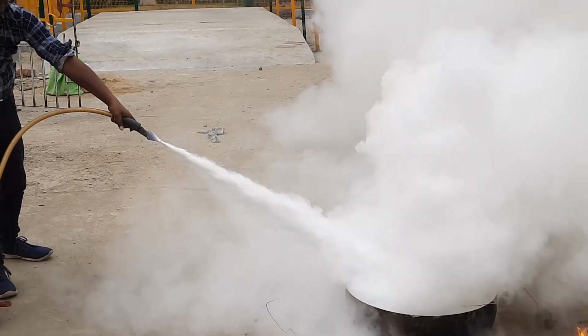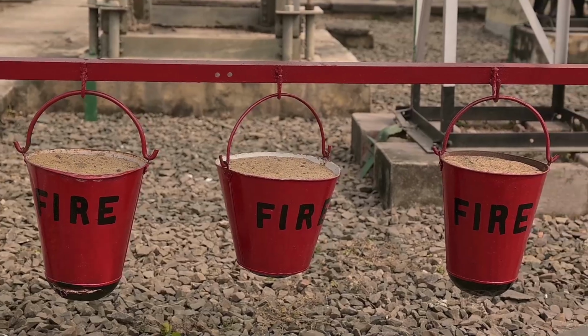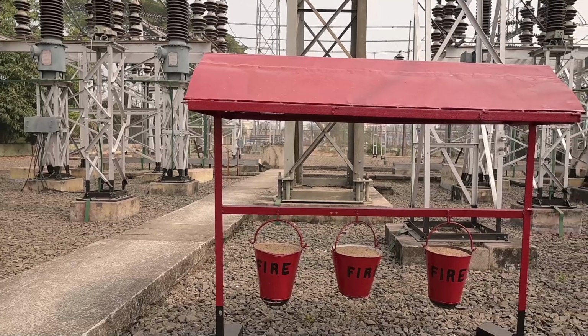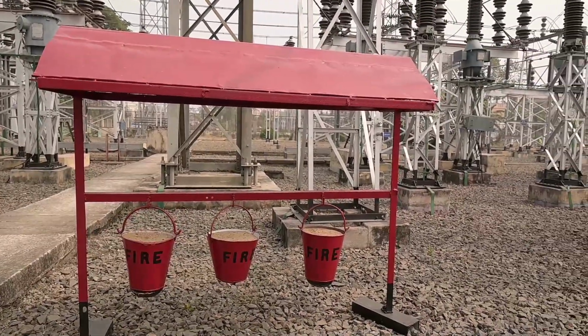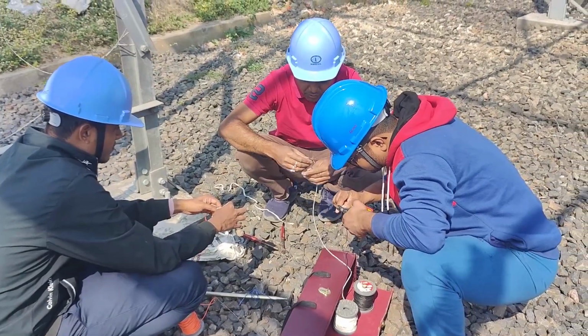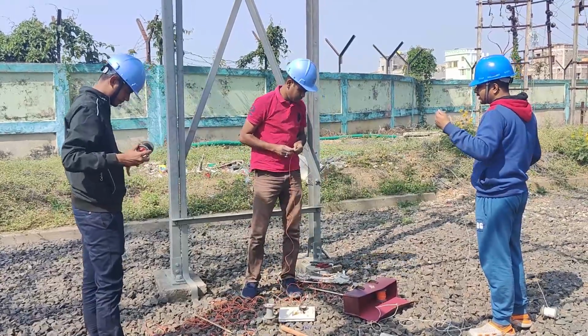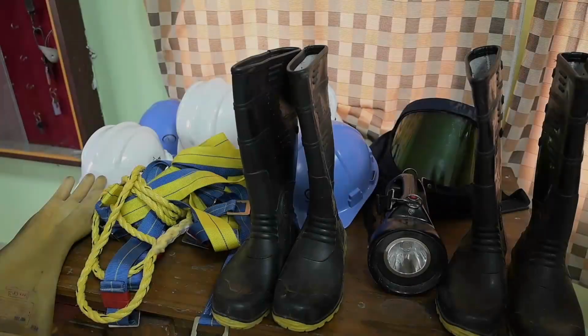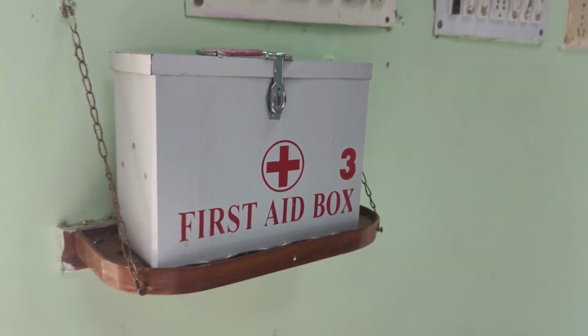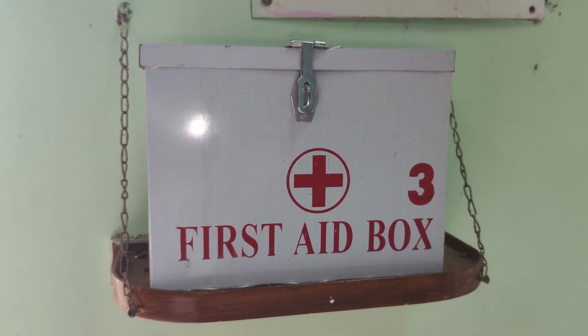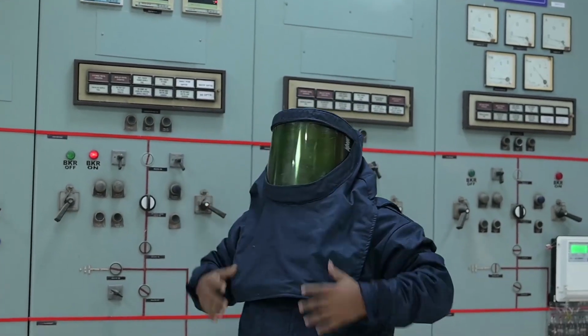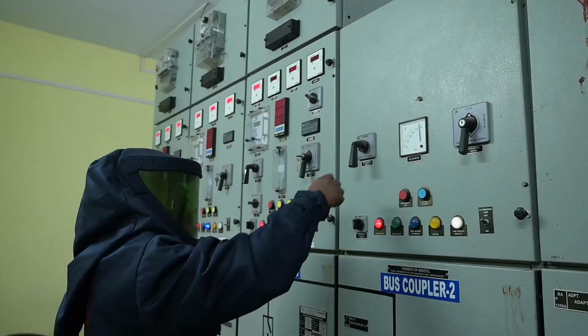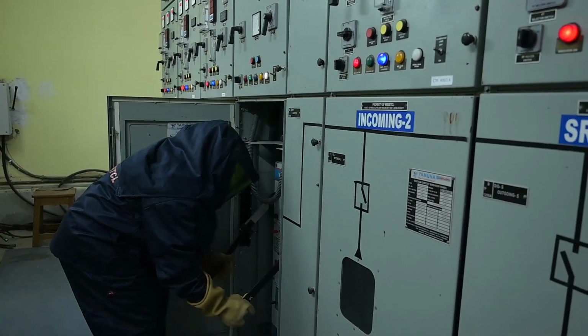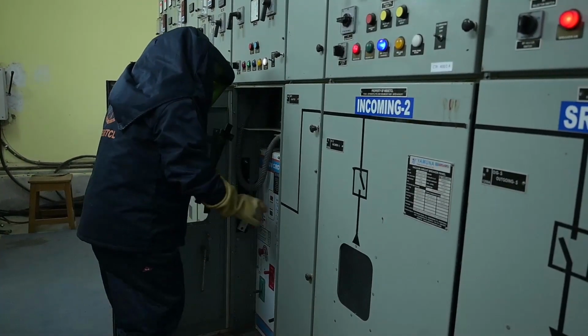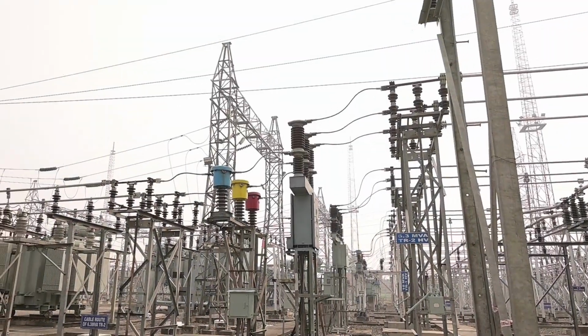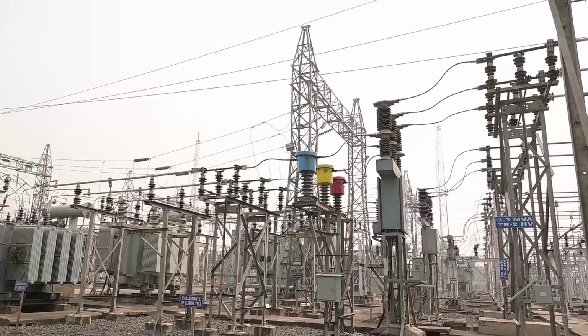The firefighting equipment such as fire extinguishers and sand buckets are placed strategically at different locations of the substation, and periodic checking of the fire alarm system is done to ensure proper functioning. Personal protective gears such as helmets, gumboots, gloves, and first aid kits are readily available at the control room. An arc flash preventive suit is also provided specially for switching operations inside the 11 kV gear room. First aid kits are routinely checked and replenished. Bay marking and phase marking are adequately done in the switchyard.